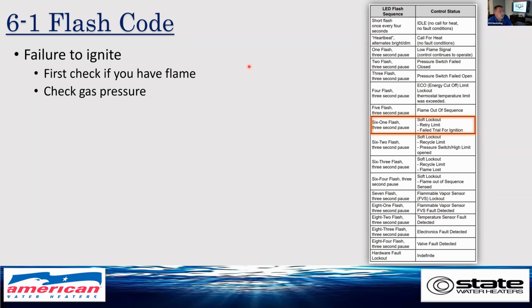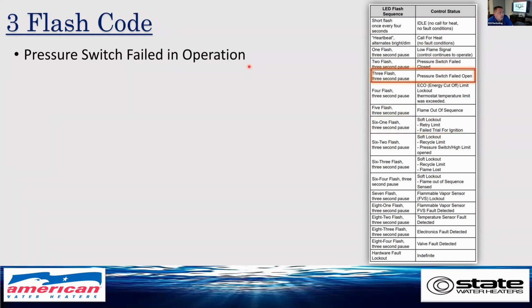If it did light, you need to look at your flame sensor. If the burner kicked on for a couple seconds and then kicked off, more than likely it's your flame sensor. Again, we would check our wiring on that and clean it. If neither of those are the cases, more than likely you have a damaged or faulty gas valve. A 3-flash code: pressure switch failed in operation. So it never closed or failed in operation.